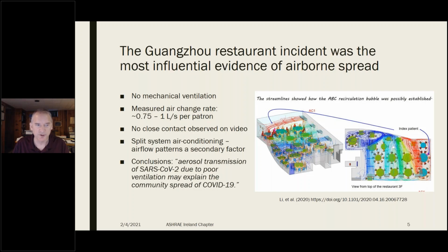The analysis revealed there was no mechanical ventilation, the natural air change rate was 1 liter per second per person or less, and video showed no close contact. It seemed fairly clear that airborne transmission was a factor, due to the concentration of infectious aerosol, affected to some extent by airflow patterns, since the infections all occurred in the recirculation zone of one split air conditioner supplying air to the 3 tables where infections occurred.